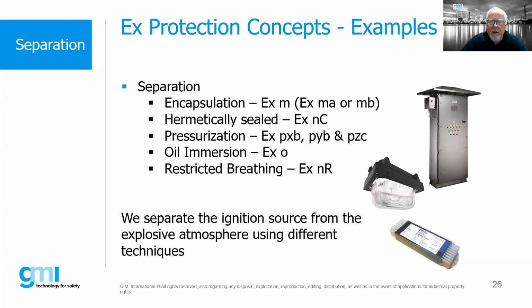Other concepts like this are encapsulation, where we take individual components such as a ballast or a relay and encapsulate them with a resin. Again, we're removing the gas-air mixture from any arcing and sparking. There's oil immersion, which is commonly used for transformers. There's also what is called restricted breathing, which is commonly used for light fittings. So these are all separation concepts.